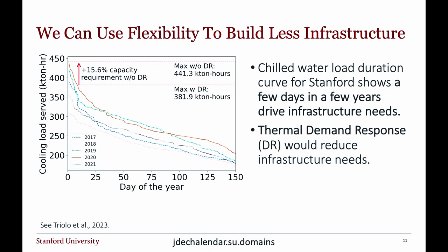The key number that comes out of this, in this case 3 years of work, is that if you had a demand response program like this at Stanford, where you increase the temperature set point by 2 degrees Fahrenheit for fewer than 10 days per year, without that program you would need 15% more infrastructure than with it. In other words, modest adjustments here significantly reduce infrastructure needs.